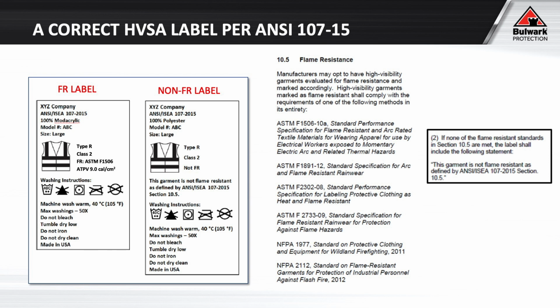How can you go and check? ANSI's done a great job of communicating what the 6 standards are that are acceptable in order to market as flame resistant. If none of those standards are met, then the garment has to tell you that it is not flame resistant. And you'll notice that ASTM 6413 is not one of the applicable standards. So there's a place to go and reference right away.